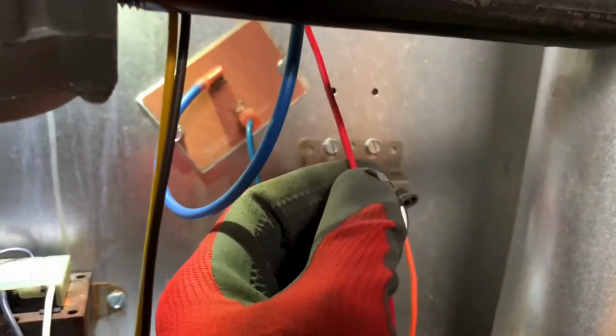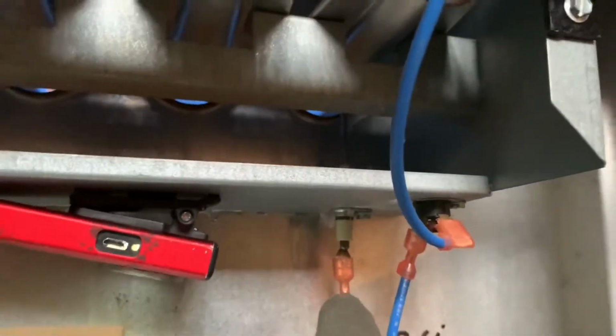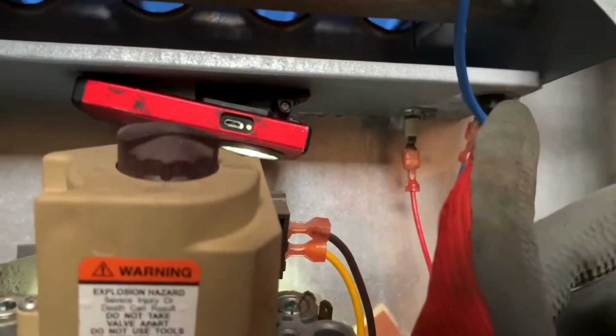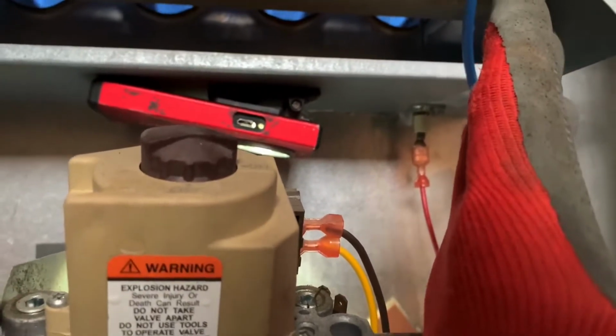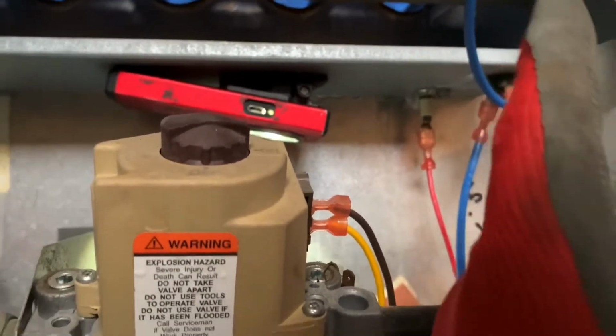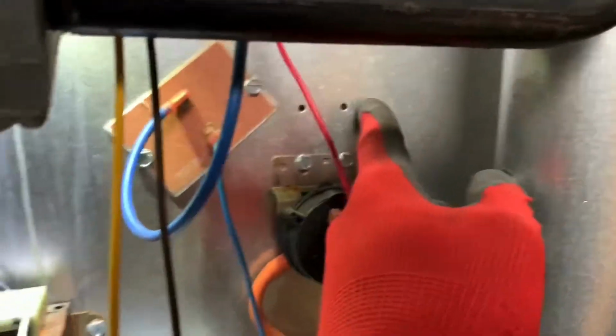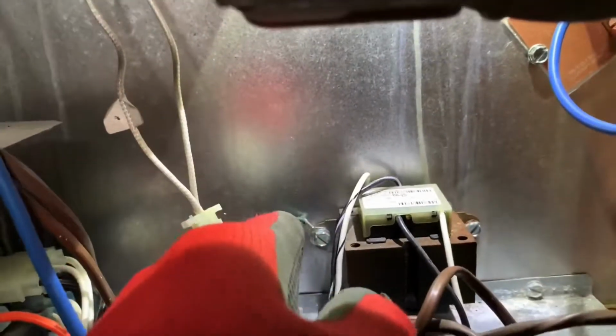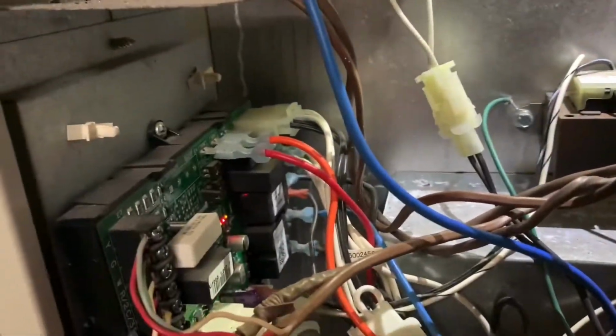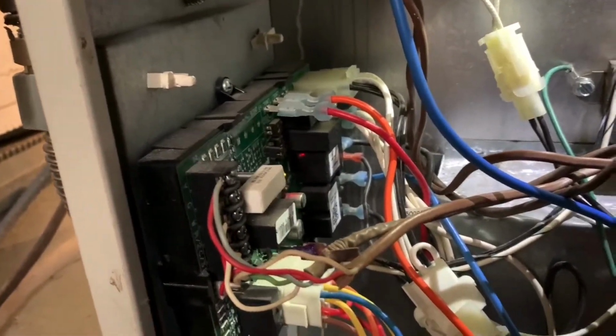So remember, this red wire here sends out the signal to the flame sensor. The flame sensor injects the signal into the flames. Then the signal goes through the flames and goes back to the chassis ground. The chassis ground wire then goes back into the board, and the circuit is completed. And that's how we know we have flame.